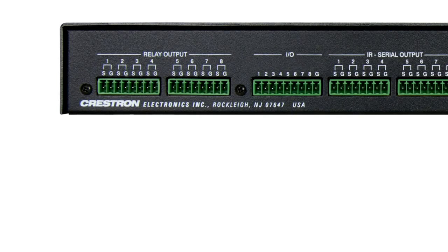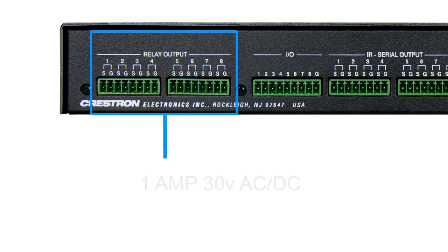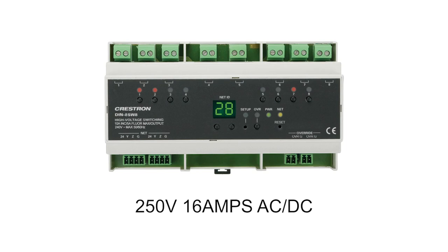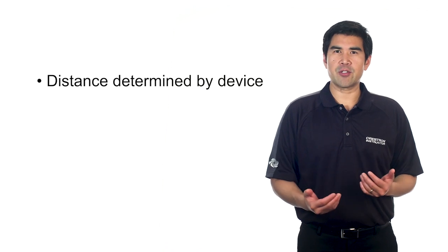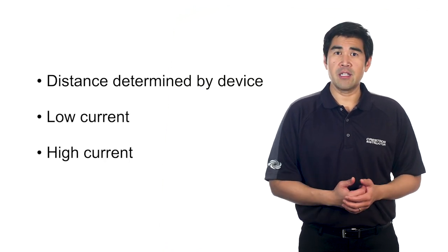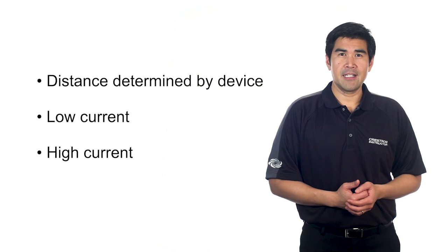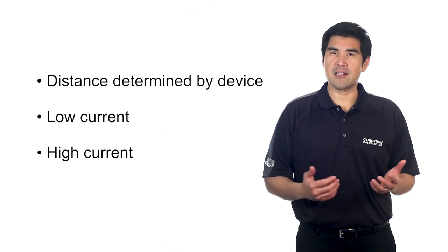The next method to look at are the low-voltage relays. On the CP3, we can see eight relay ports on the very left-hand side. These relays connect directly to the device we wish to control. The relays available on most processors are rated at 1 amp, 30 volt AC/DC. If you need to switch to a higher current voltage, other units are available. The distance is determined by the device — as it's a contact closure, we could be switching very low or high current. Relays can be used for any device that requires a contact closure.